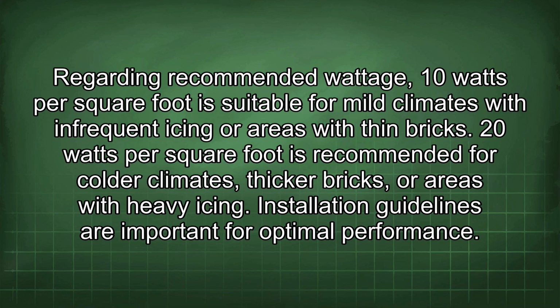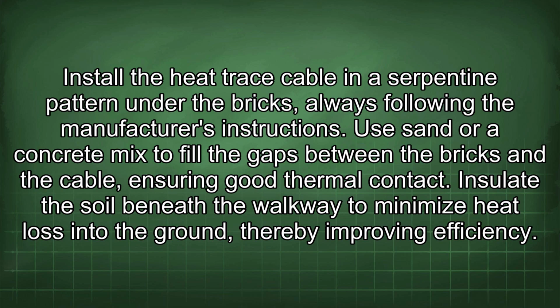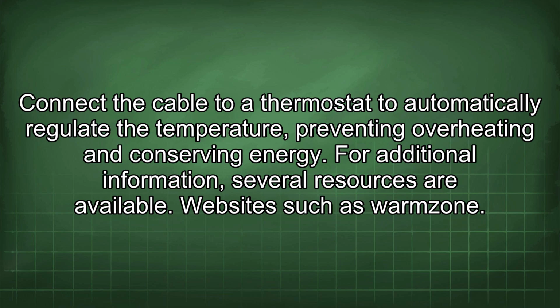Installation guidelines are important for optimal performance. Install the heat trace cable in a serpentine pattern under the bricks, always following the manufacturer's instructions. Use sand or a concrete mix to fill the gaps between the bricks and the cable, ensuring good thermal contact. Insulate the soil beneath the walkway to minimize heat loss into the ground, thereby improving efficiency. Connect the cable to a thermostat to automatically regulate the temperature, preventing overheating and conserving energy.